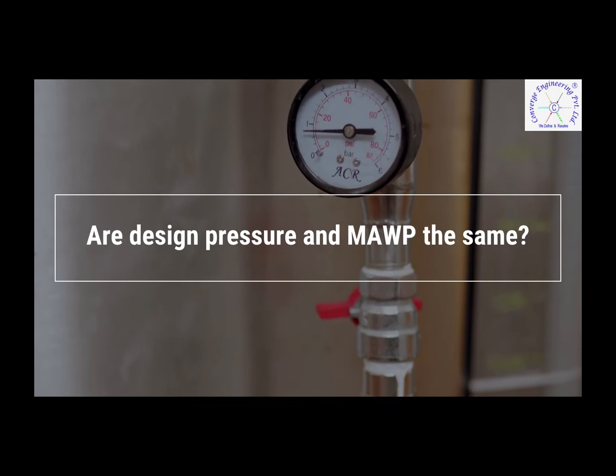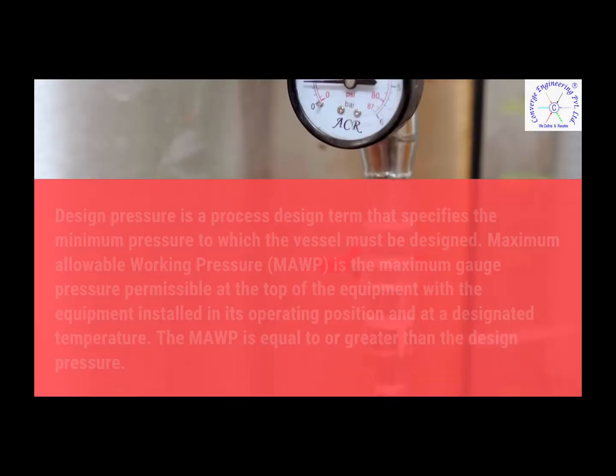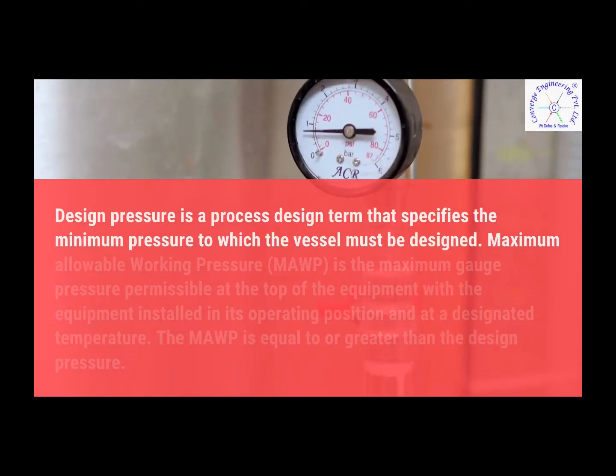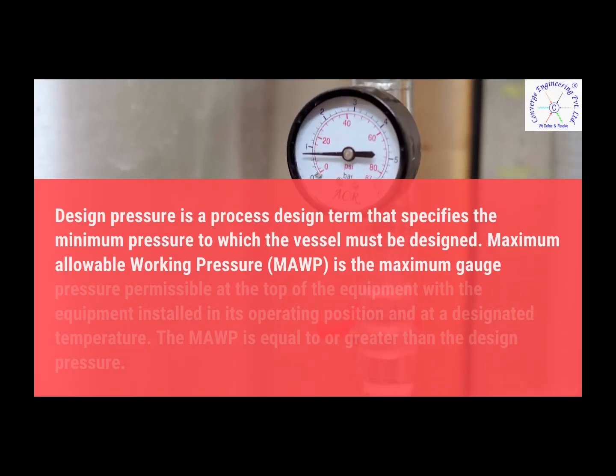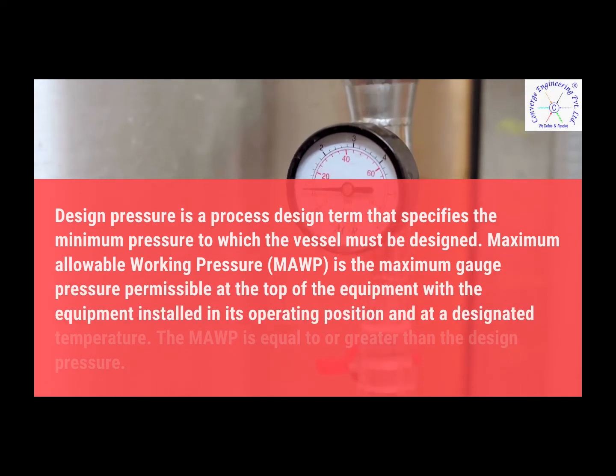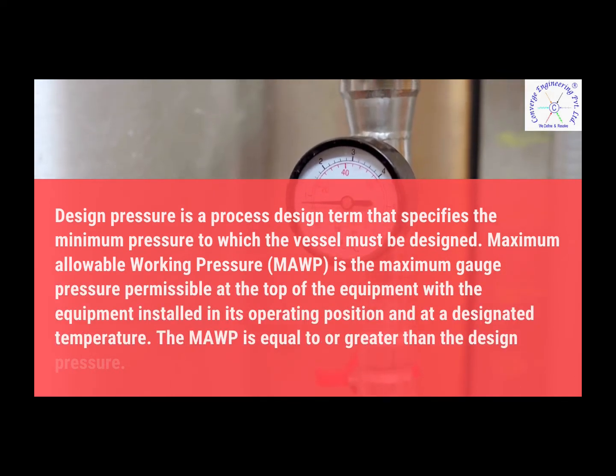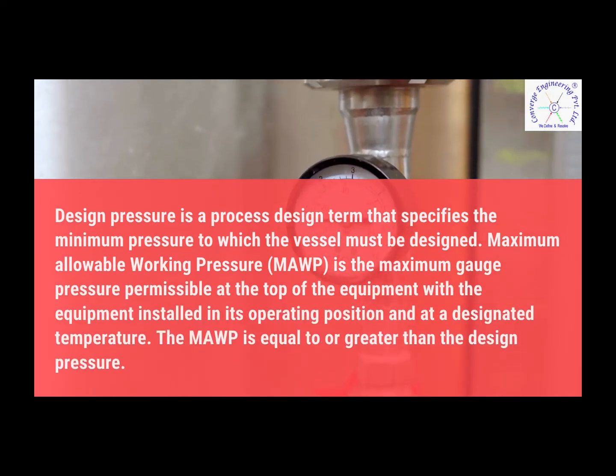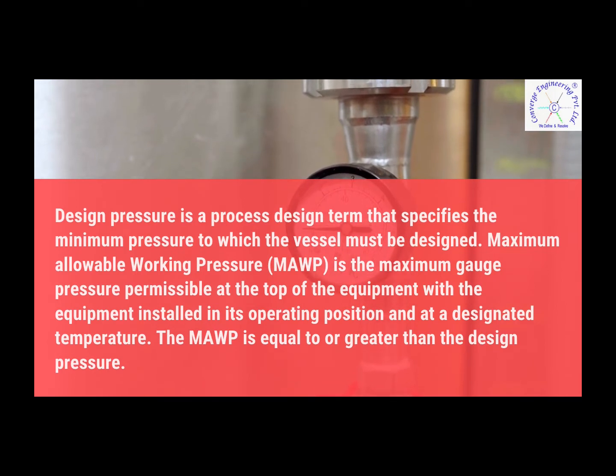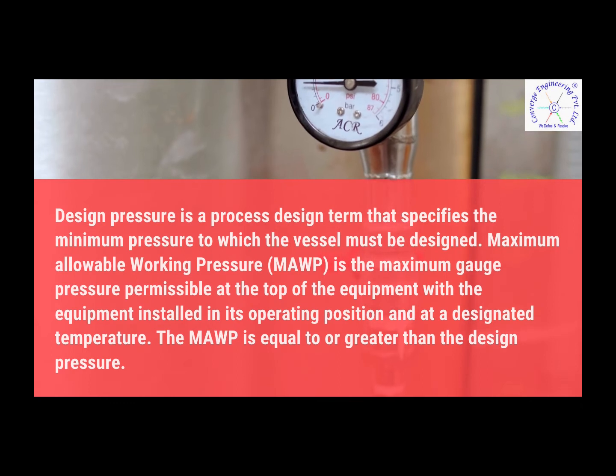Are design pressure and MAWP the same? Design pressure is a process design term that specifies the minimum pressure to which the vessel must be designed. Maximum allowable working pressure (MAWP) is the maximum gauge pressure permissible at the top of the equipment, installed in its operating position at a designated temperature. The MAWP is equal to or greater than the design pressure.